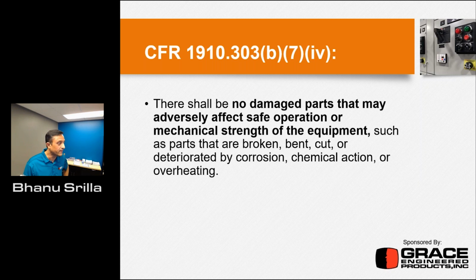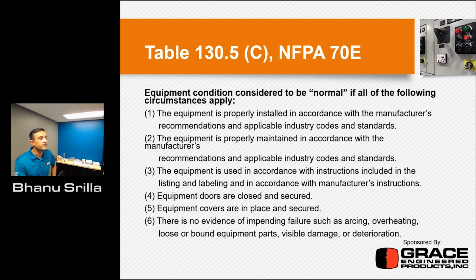So this is Table 130.5(C) taken out from NFPA 70E, which considers equipment condition to be normal if all of the circumstances apply. So if you look at steps 1 through 6, this is primarily talking about the equipment being properly installed in accordance with the manufacturer recommendations, which goes to NFPA 70, the NEC code. The equipment is properly maintained in accordance with the manufacturer guidelines and applicable industry codes, which is again what we talked about on the conditions of maintenance, right? And then the third bullet is the equipment being used in accordance. So you need to make sure the equipment is not used beyond what it is designed for.